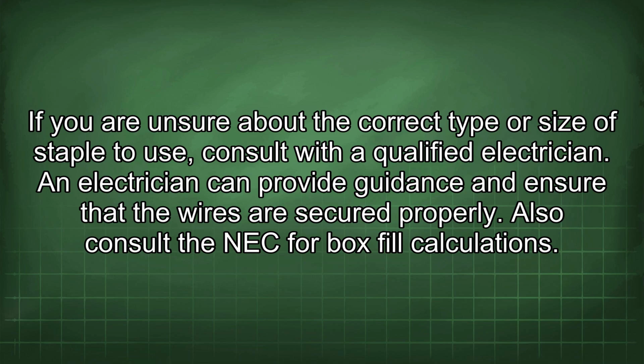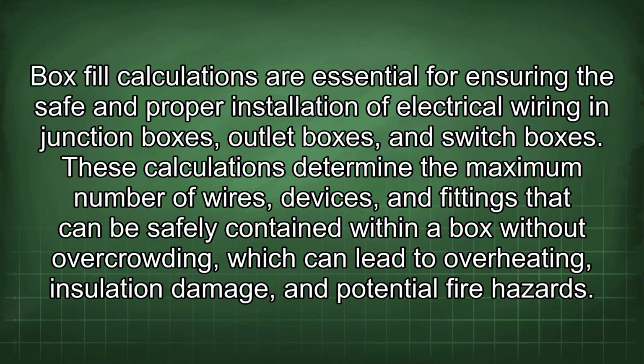Also consult the NEC for box fill calculations. Box fill calculations are essential for ensuring the safe and proper installation of the electrical wiring in junction boxes, outlet boxes, and switch boxes. These calculations determine the maximum number of wires, devices, and fittings that can be safely contained within a box without overcrowding, which can lead to overheating, insulation damage, and potential fire hazards.